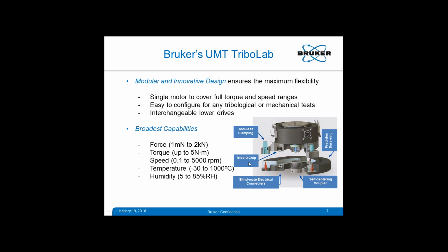We also have a Tribo ID chip which enables plug-and-play procedures. Whenever you connect a drive, the system automatically detects it and loads the optional features, like the maximum speed in case of a motor, or if you are adding some kind of environmental chamber, what is the maximum temperature it can go, and all other parameters.